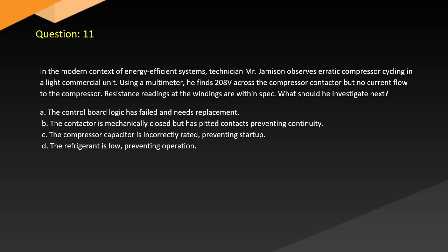A. The control board logic has failed and needs replacement. B. The contactor is mechanically closed but has pitted contacts preventing continuity. C. The compressor capacitor is incorrectly rated, preventing startup. D. The refrigerant is low, preventing operation.